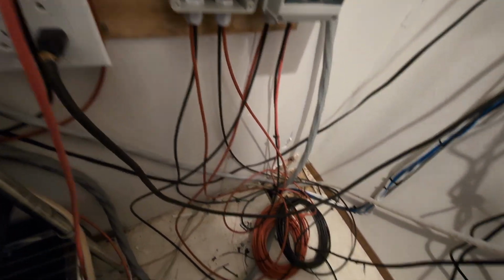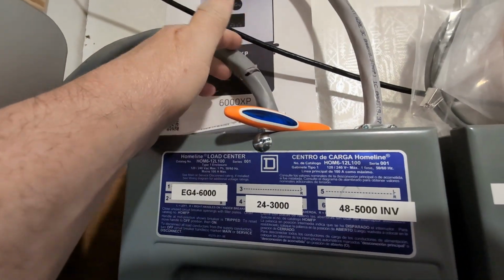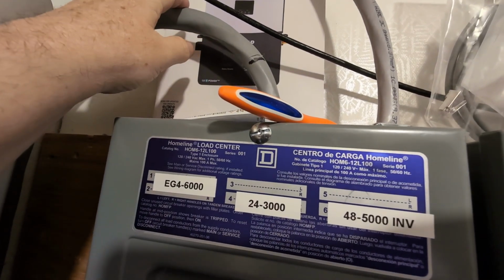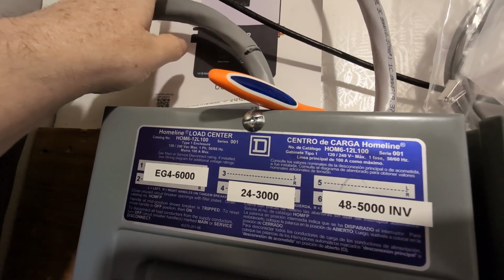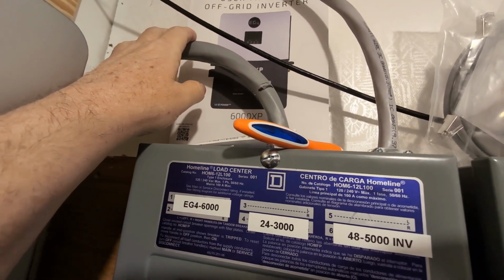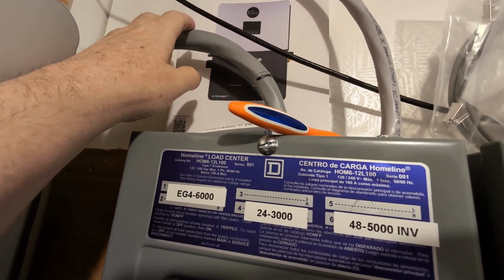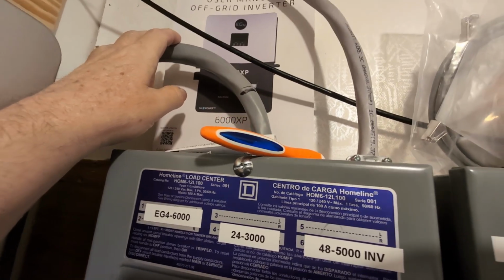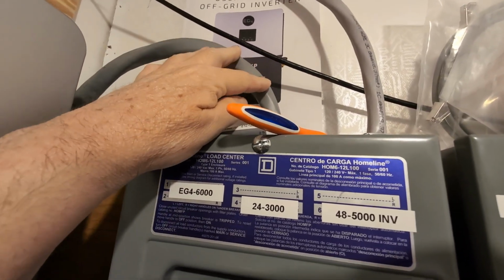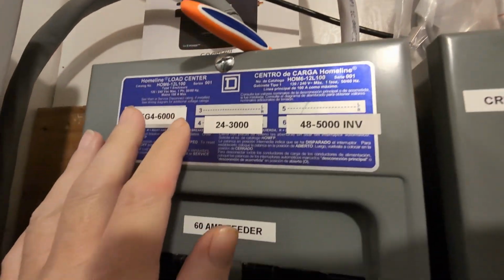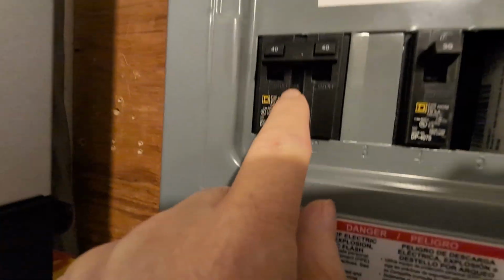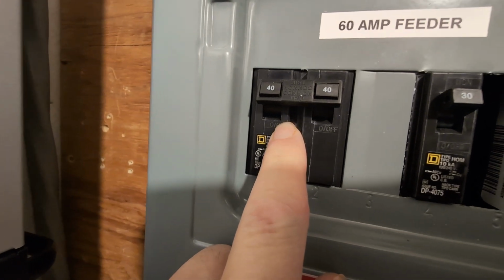And this goes over to the equipment room. So the main power for the grid feeds in through the floor here, comes up this large service entrance cable right here, capable of 100 amps. I wanted plenty of ability to grow my system. So this wire, even though I'm only pulling about 30 to 50 amps through here, I sized it for 100 amps. So that feeds in here via a 60 amp breaker from my main panel. So this is where the grid power comes in for the EG4, which is a 240 volt inverter. That's a 40 amp feed right there.